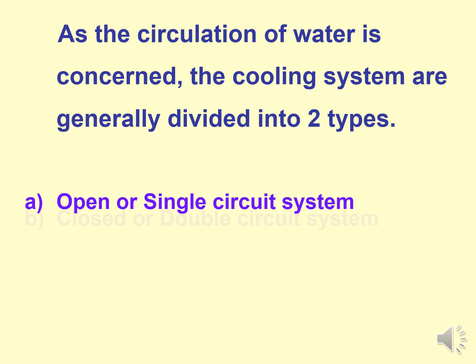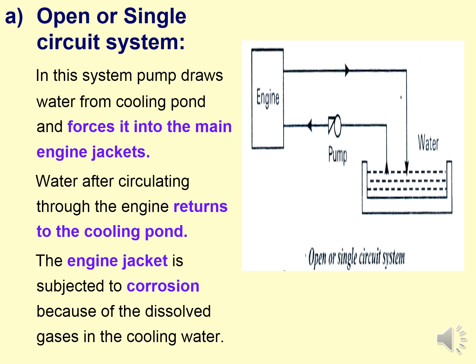In the open system, water is stored in this tank. From this tank, water is pumped to the engine, circulated, and comes back to the sump. So this is a single or open system, not a closed system. Engine jacket corrosion can occur because of dissolved gases in the cooling water in this type of system.